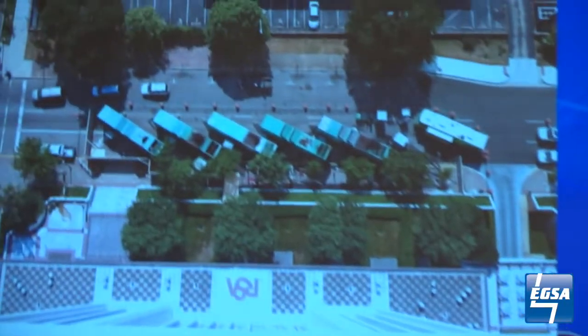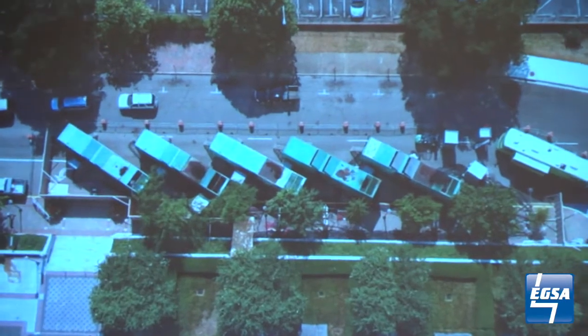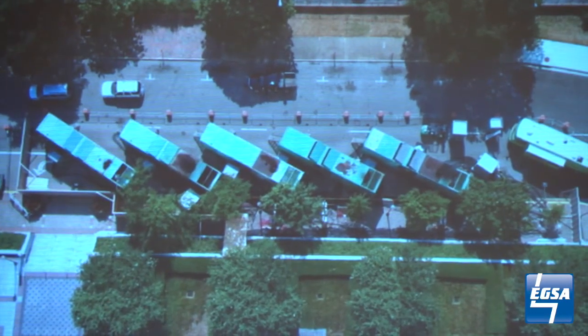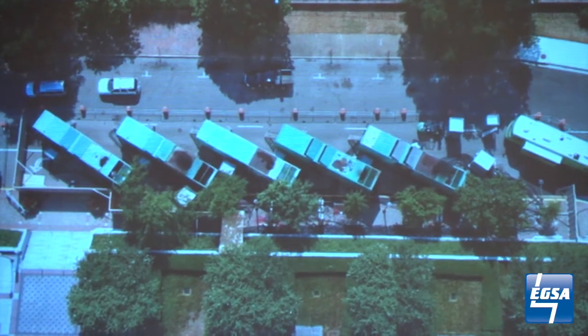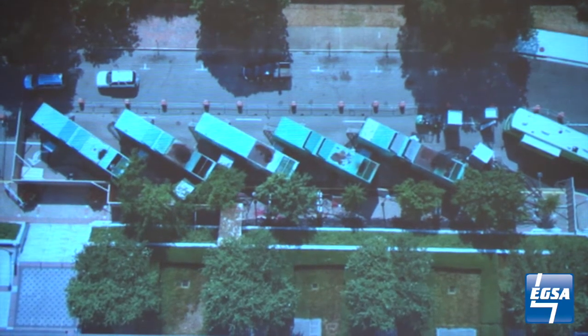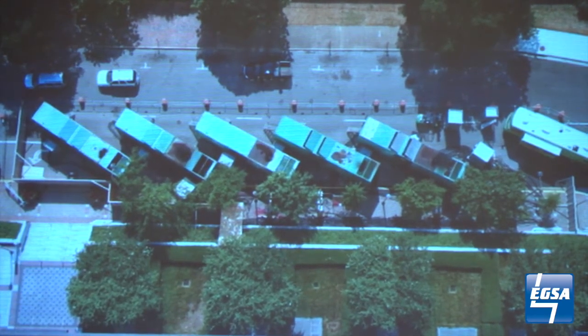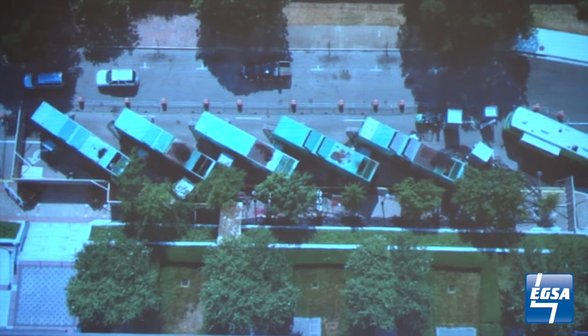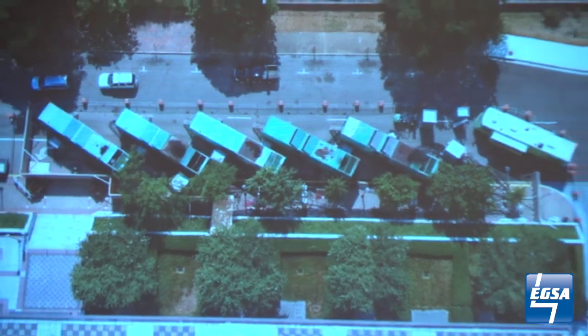So the three generators on the left-hand side in this picture were supporting the critical load. If you look close, you'll see the first two from left to right have the louvers open - the one in the middle has the louvers closed. It was connected and parallel ready, a redundant system - one machine could handle everything. So we would run both, split the load. If one would go down, the second would come in, and the third one was a backup to the first two. On the other side, it was less critical load, so we just had two 1500s.